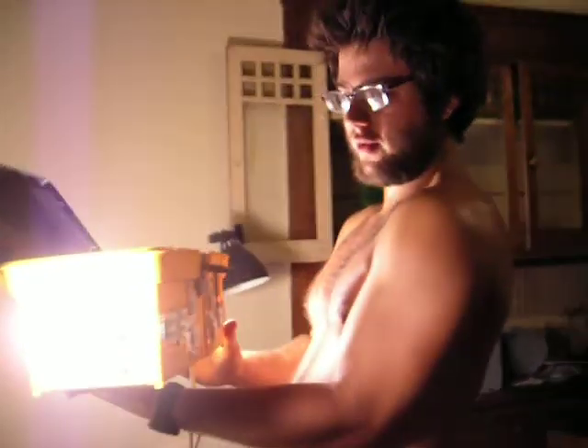So our on-off switch, how I wired this, the thing to remember to wire the polarity of a socket, of a plug correctly, is brass is black and silver is white. The screws on the side are actually silver for the side that you're supposed to connect to the white wires, and they're brass, like a brownish color, for the ones you connect to the black. So we've got it wired up with the correct polarity.